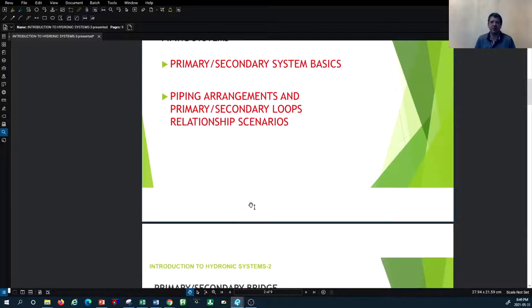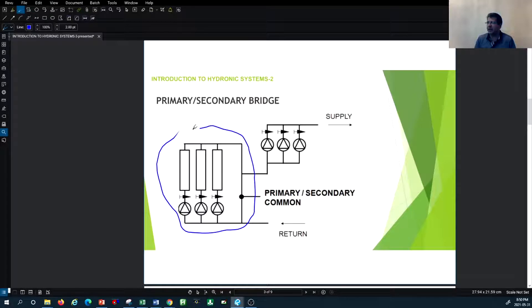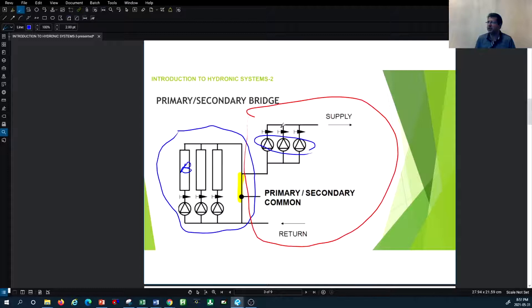We're going to look at the relationship between the primary and secondary loops and how temperature changes in these two systems. In this example, you can see a number of sources. The primary loop is on the left-hand side, and the secondary loop is on the right-hand side. They are interconnected through what is called a common bridge or common pipe. In this example, you can assume these are boilers — three boilers with recirculating pumps on the primary side and secondary pumps distributing hydronic fluid to building loads on the other side.